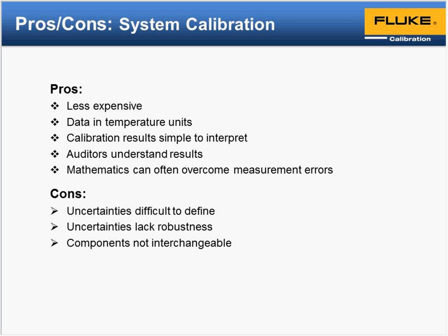Sometimes system calibrations are not offered for particular pieces because they require a higher level of uncertainty, and the process doesn't allow for that — it just can't be quantified in a particular process. So these are just things to keep in mind as you're doing your calibration work.